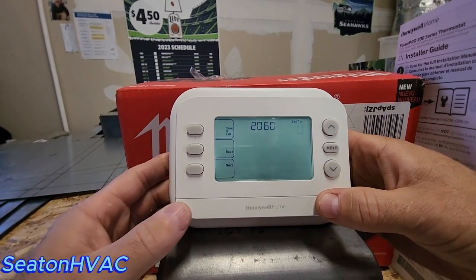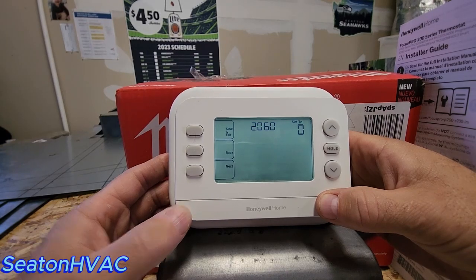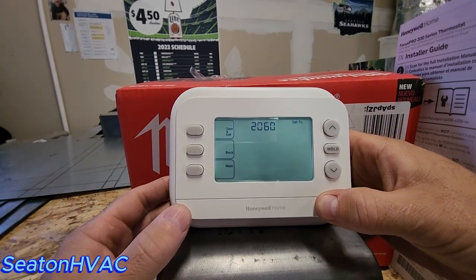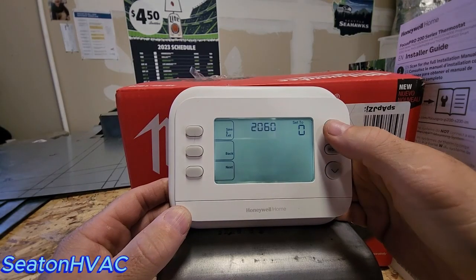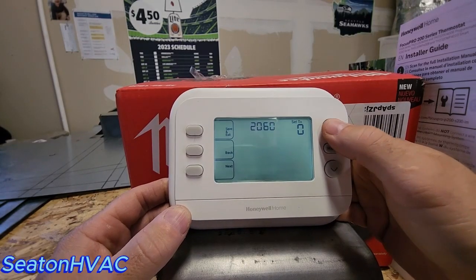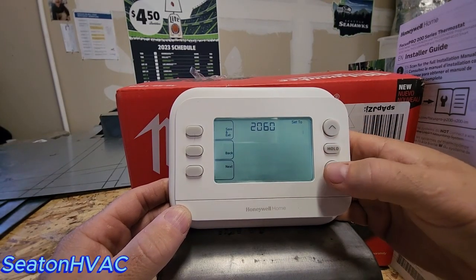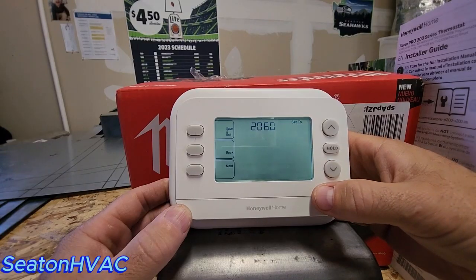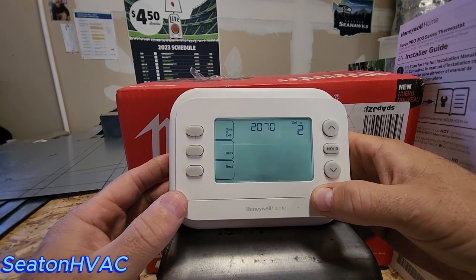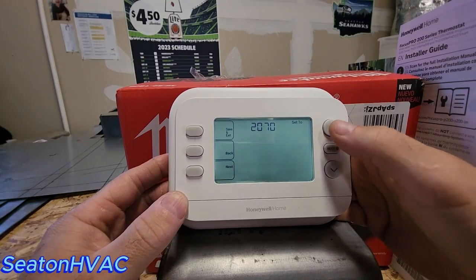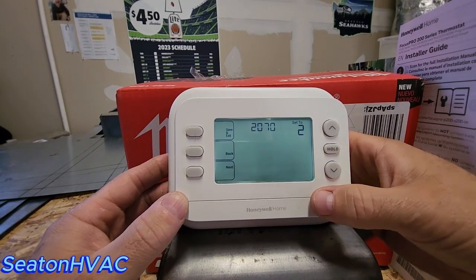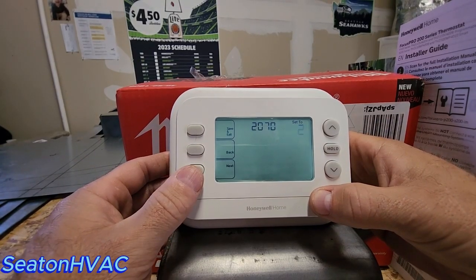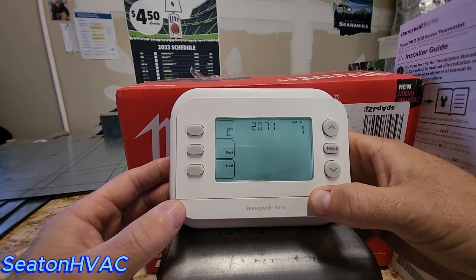Leave that there. And then reversing valve, like the Bosch and Rheem I install, are B, so you would switch that to 1. A lot of other systems energize on O, so you would leave that at 0. Compressor stages, that's pretty self-explanatory, 1 or 2. This is a two stage compressor, let's say, so you can put that at 2.